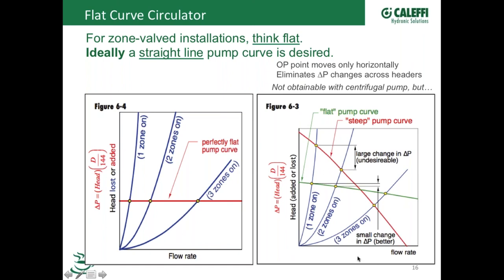now what you're going to notice is a velocity increase. You're going to start to hear noise in those zones that are still on, because now you're increasing the rate of flow going through there, and you'll get noise and obviously can get wear and stuff like that. So the flat curve pump is the one you want to choose.